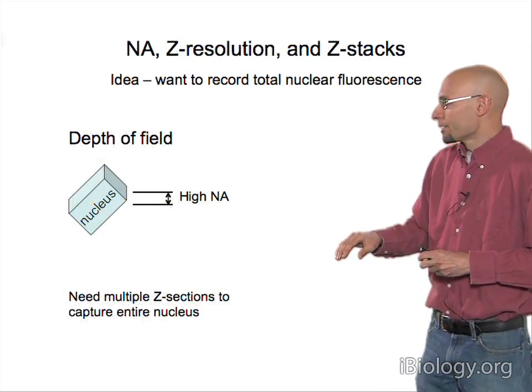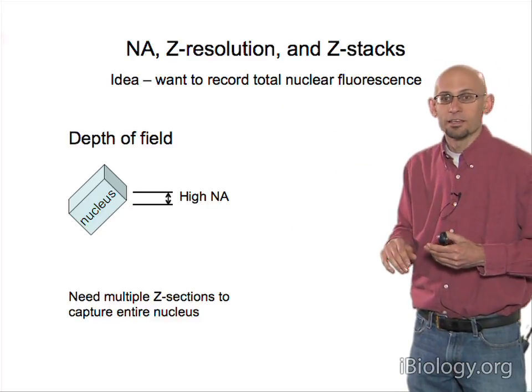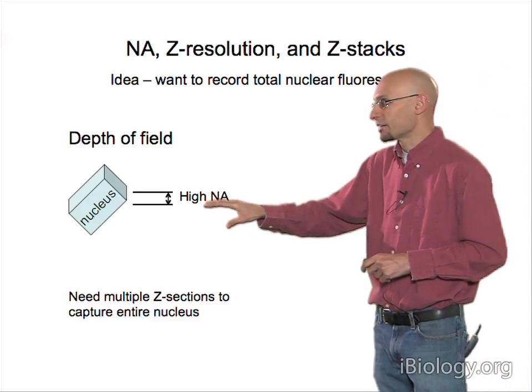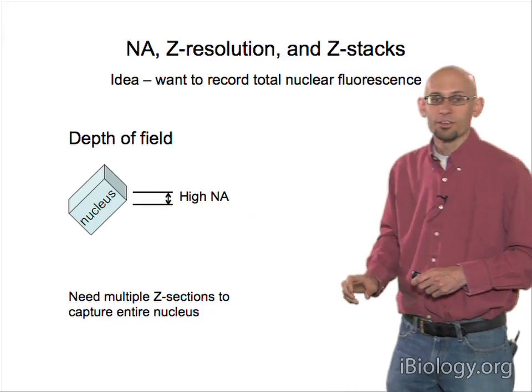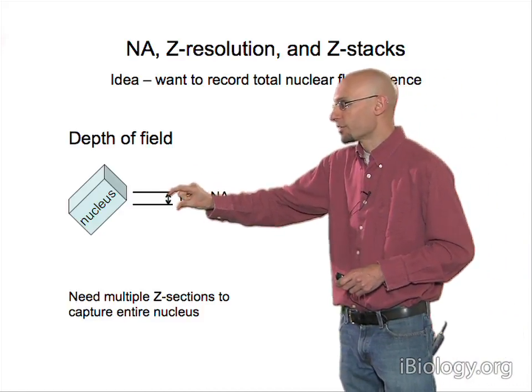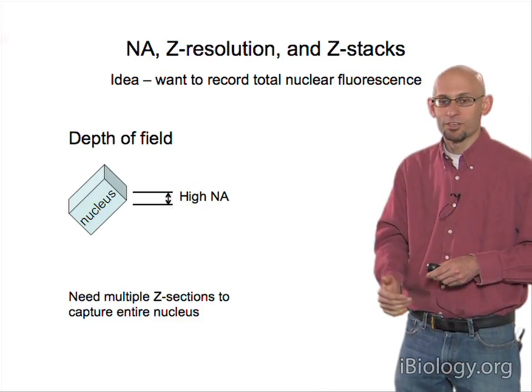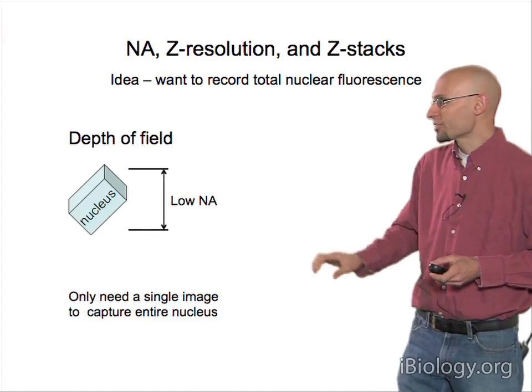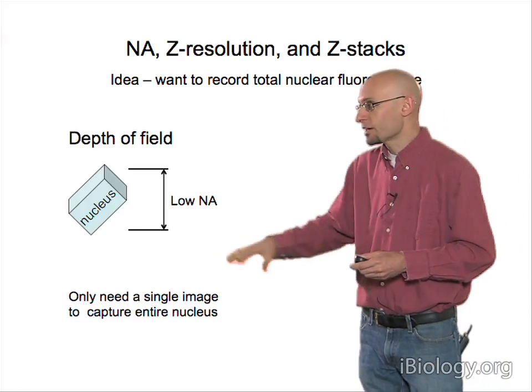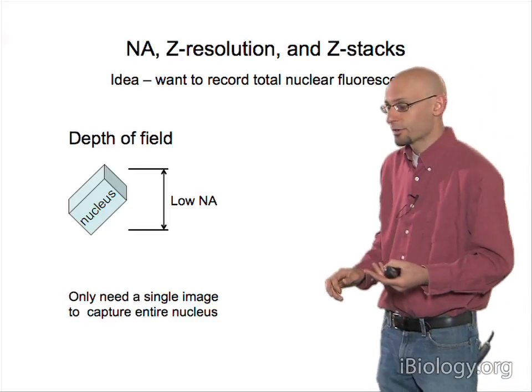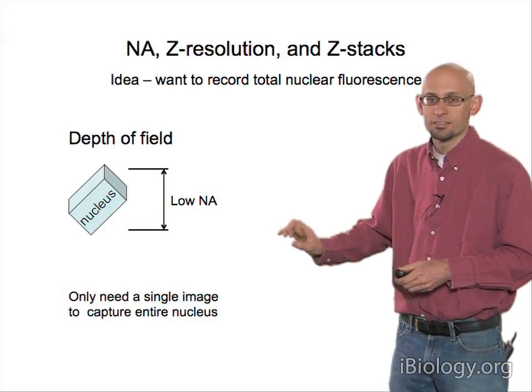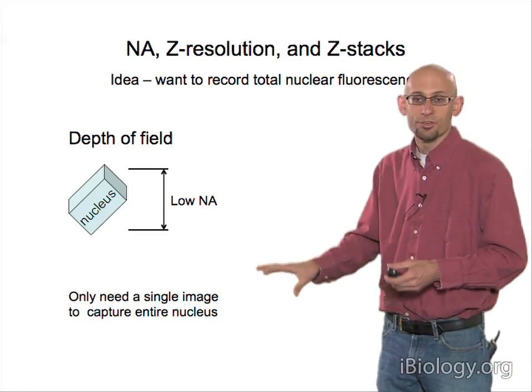For example, if you want to record total nuclear fluorescence to measure transcription factor abundance, a high NA objective gives just a thin band in focus at any one time — only a small chunk of the nucleus — so you'd need many Z sections. Switching to a low NA objective gives a much larger depth of field, capturing the whole nucleus in focus in a single section. The trade-off is lower light-gathering power and dimmer images, but if nuclear fluorescence is reasonably intense, this is a faster and more efficient approach.